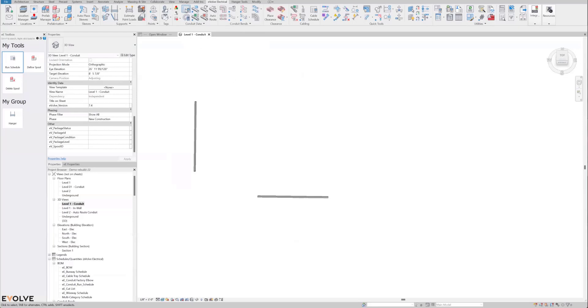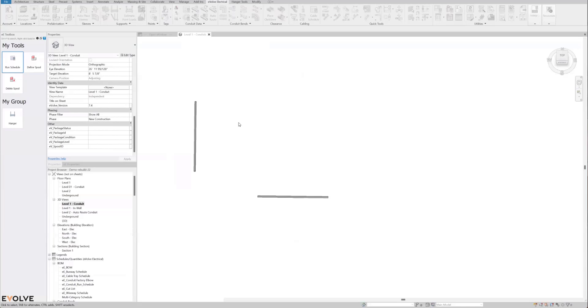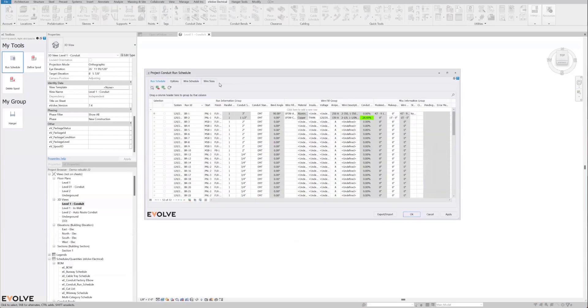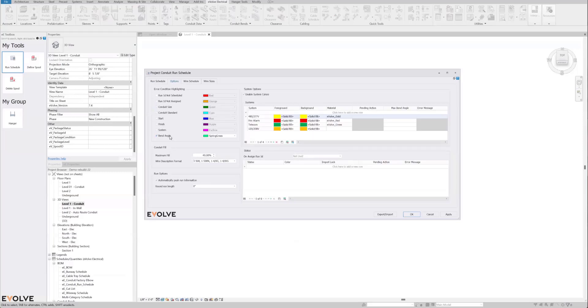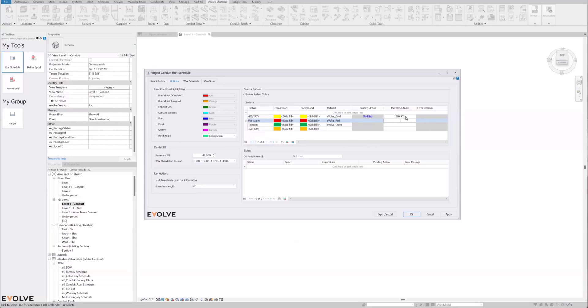We also have some enhancements to the Conduit Run Schedule. Over in the options, we now have a new condition within the error condition highlighting, which is the bend angle. You can set a max bend angle — for example, you don't want any of your conduit runs to exceed 360 degrees of bend. You can define that for your different systems, and as they exceed it, it'll change the color based on what you have selected. It's a nice QA/QC tool — whatever your max threshold is for the bend angle, you can define that and set up the coloring rules for when the color changes.